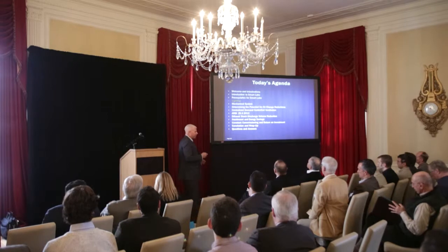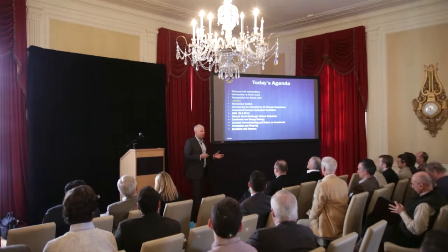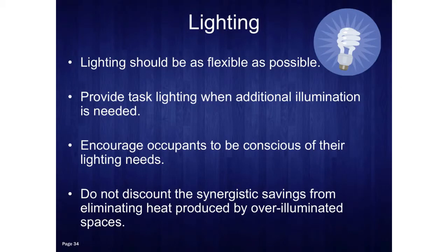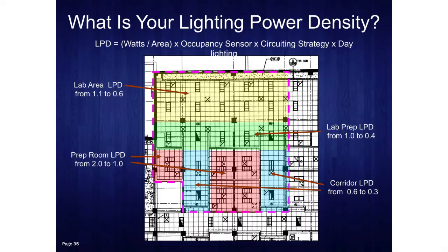So with that, we've gotten through the prerequisites. Now we can get into the first piece of the laboratory, which for us right now is lighting. Lighting seems to be where most people start, so we figured that's where we should start today. What do we want lighting to be? We want it to be flexible and dynamic. We want people to take advantage of the fact that we've put in some ability for them to control their lighting, so we can save energy automatically, and we want to encourage people - we want to have that conversation, be conscious of your lighting needs. We'll look at ways that we do that. So we started out by asking, well, what's the lighting power density of the space?